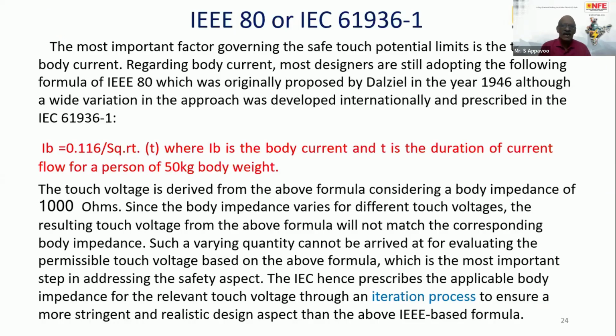Then I am coming to another point, that is IEEE 80. Most of the damage to the consumer installations does occur, and the HV substations play a vital role in containing the over voltages getting transmitted to the subsequent substations. That's why they have to provide standard measures to contain the earth fault current or to minimize the voltage rise, that is the touch voltage. So we are simultaneously observing IEEE 80 and IEC 61936, which is correct, I will deal.